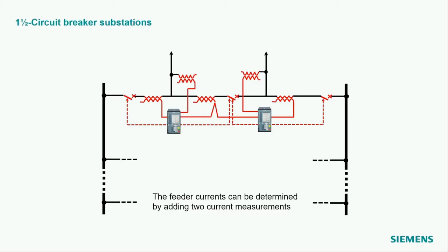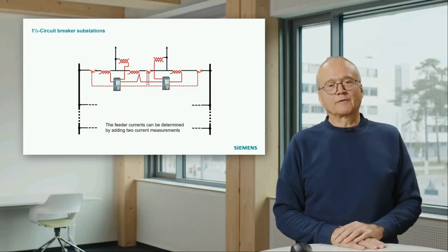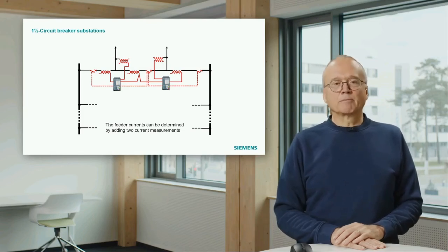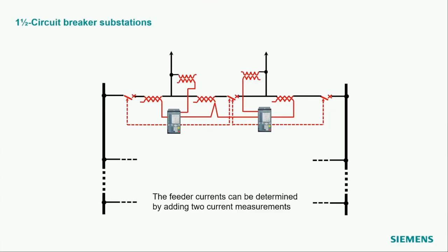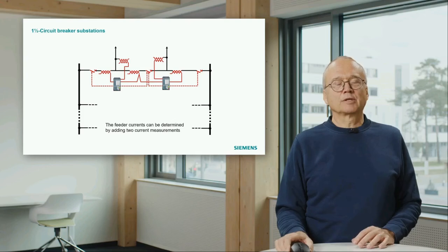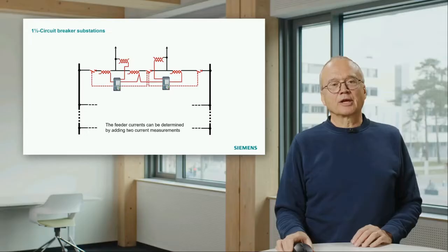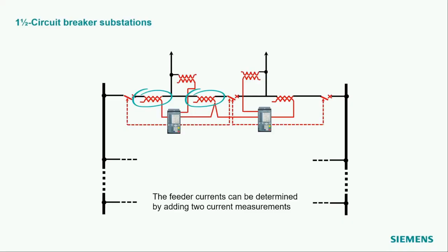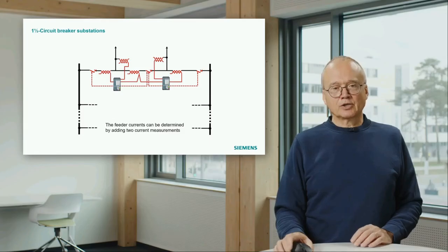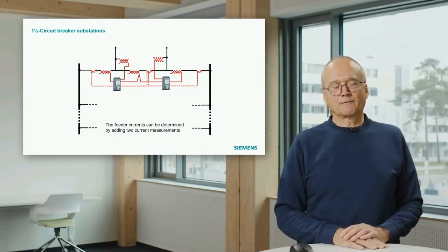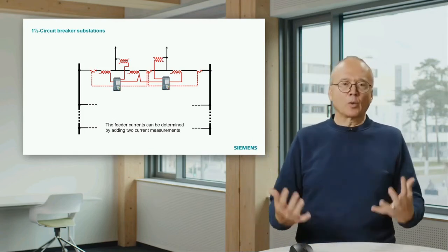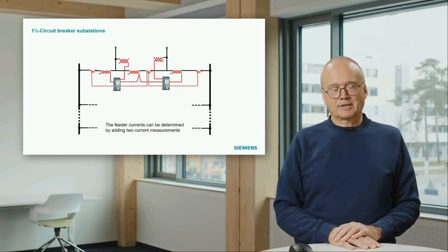In this case, the situation with the voltage transformers is pretty easy. So we have a voltage transformer on the feeder. That means the left-hand relay measures the voltage on the left feeder. The same applies to the right one. The current measurement is a bit more tricky in this case. As you see here, the current transformer is not in the feeder. The current transformer is here, or several current transformers are here in this so-called diameter. Diameter is this horizontal connection between the 2 bus bars. And in order to measure the current in the feeder, for instance in the left-hand feeder, the protection relay has to sum up 2 current measurements in the diameter, and just by summing up the currents it can measure the current in the feeder. But the rest behind that, the protection principle, the way to identify short circuits, is the same as in the previous drawing.